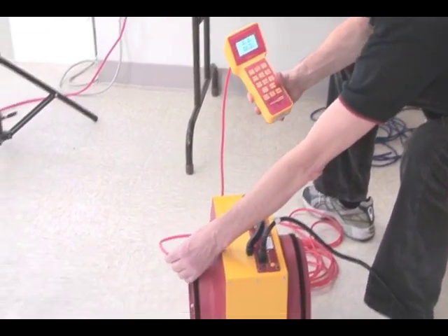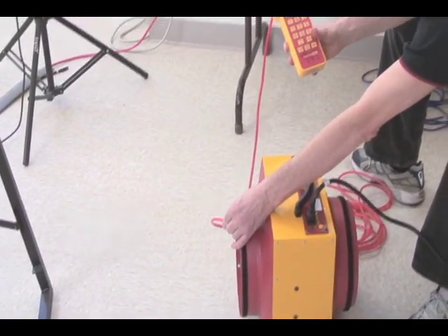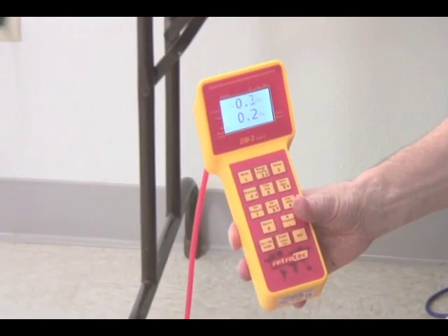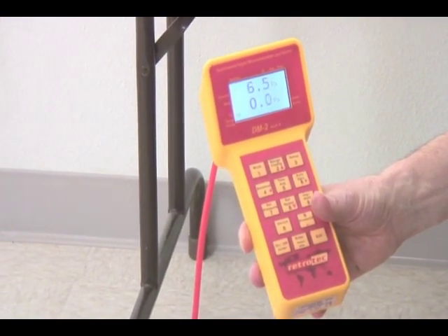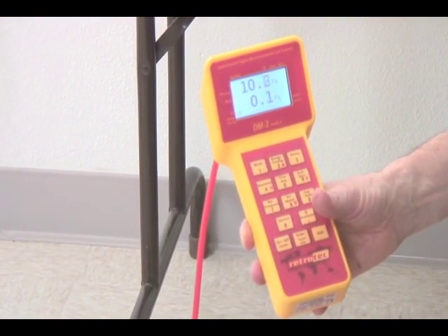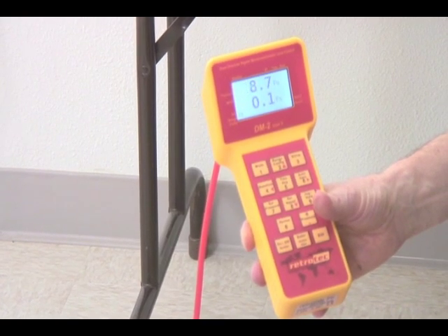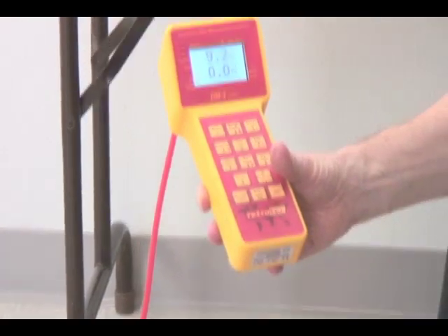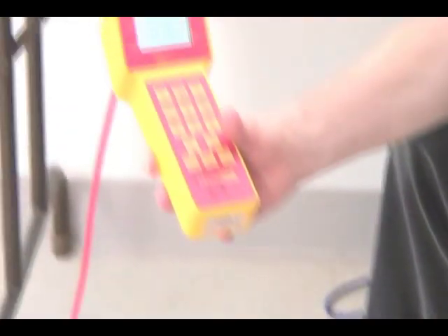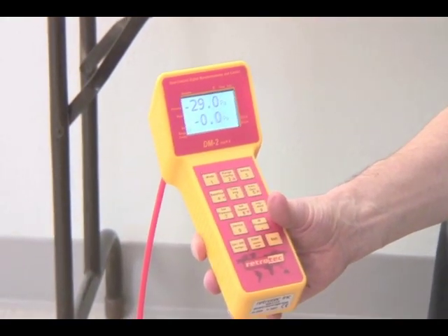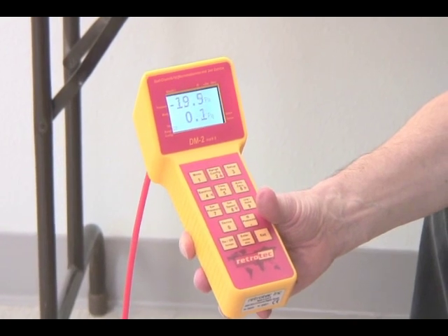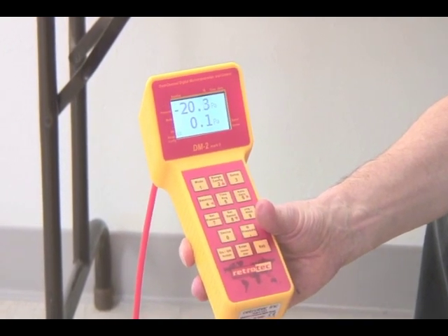So we're just going to take our tube here and hang it in the wind stream, and you'll notice that the pressure is going to a pretty high positive value. It's also bouncing around. It went to plus 6.5, plus 10.2, plus 12.7, and so on. Now, if I put it on the inlet side where I have a suction pressure, which would be equivalent to the downwind side of the house, I have a big negative pressure there. So we can see that the wind has a huge effect on the reading on our gauge.